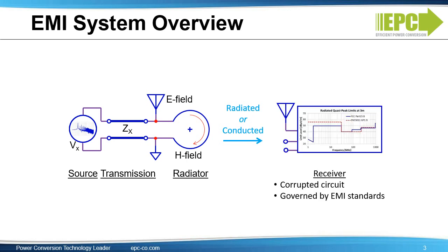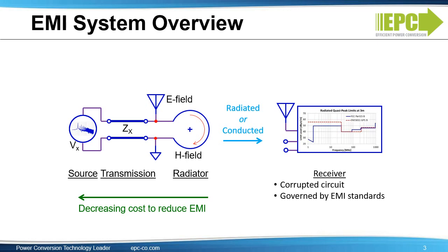The final component in an EMI system is the receiver, which by definition is a circuit that becomes corrupted, leading to undesirable behavior. The receiver circuit can be the same circuit that includes the source, or a third-party circuit, for example a radio receiver. In the case of third-party receiver circuits, the prevention of EMI-induced undesirable behavior is governed by EMI standards. Addressing EMI mitigation measures inevitably adds cost to a system, and the closer to the source that the measures are employed, the lower the cost they become.